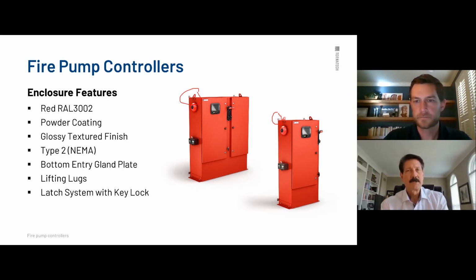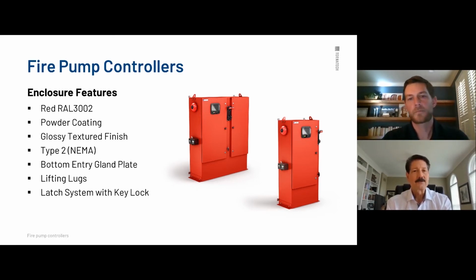So, Cole did mention on incoming, as an alternative if you can't come in the bottom, you can come up the side of the back of the first 12 inches of these enclosures because they're encased. Again, there's a whole different set of guidelines and rules. If you must come in the top, we can talk about that later. But any entry into this enclosure other than coming in the bottom is going to require a watertight hub. That is in our manual. Even though this is NEMA 2, which is kind of like drip proof, very light dripping from the top, we require any entry, and this is by electrical or even alarm people, to have a watertight hub just to protect the internal components.